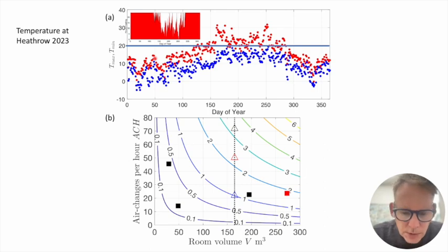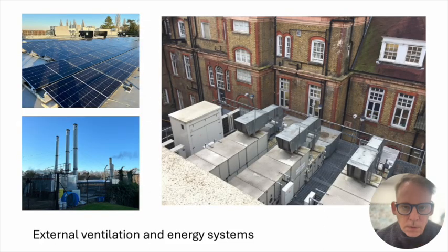Overall, it's about 1.8. The vertical line here shows a typical room volume for a theatre in the UK, 55 square metres floor area, 3 metres height. And the triangles show the volumetric airflow for ultra laminar flow facility, temperature controlled, and also conventional. To condition the air to a nominal 20 degrees centigrade in the theatre, we need air handling units which draw in air from outside and precondition it so that it can enter the hospital operating theatre.